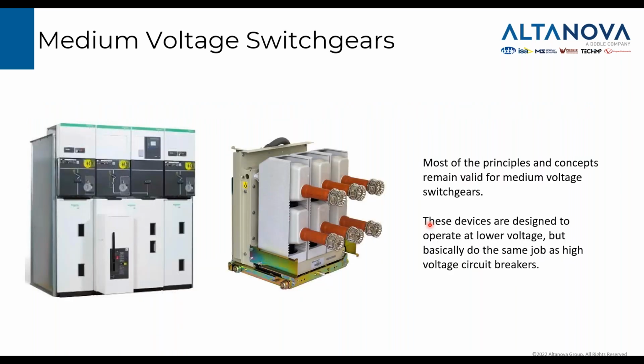In the case of medium voltage switchgears, the concept remains the same. In medium voltage switchgear, you will find only one break per phase, and the dimension is much less. These devices are designed to operate at lower voltage. That's why the size is much less. But again, the testing principle is the same as for a high voltage circuit breaker.